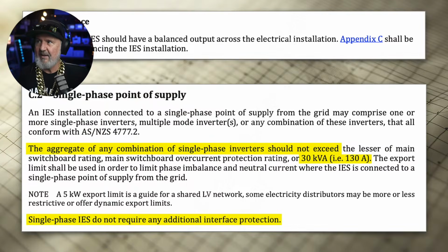The 5 kilowatt export limit is a guide when you've got a shared low voltage network. A lot of this stuff comes down to the DNSP, or in the case of New Zealand, lines companies' rules. I think New Zealand's got something like 26 lines companies, so it's quite a lot for a small country. But they all have their slight variations on rules. So even though the standard might say you can go up to 30 kVA on a single phase installation, you still have to get an approval for that.